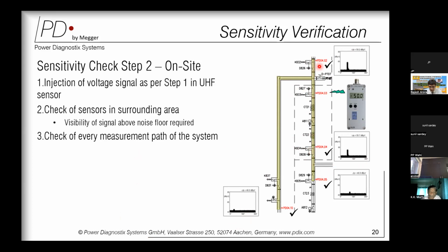can say that the point between sensor number 2 and sensor number 4 is qualified to capture 5 PC pulse. If the pulse is applied here, both the sensors are capturing. If PD in origin is shifting to sensor number 2, the pulse at sensor number 2 will respond with a higher magnitude. And if PD is moving towards sensor number 4, the point number 4 will result with a higher amplitude.